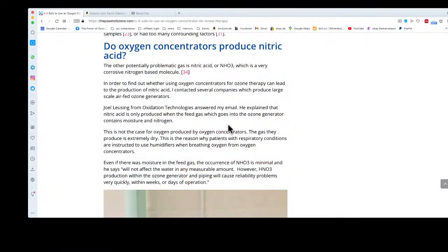So even if nitrogen oxides are produced during the usage of oxygen concentrators, there is no reason to believe that this could be somehow detrimental to your health. And if there is nitric oxide, so NO, this could actually even be beneficial, as crazy as this may sound. But apart from nitric oxide, so apart from NO and NO2, nitrogen dioxide, there's also another gas that can be produced. This is nitric acid, or HNO3. And this is a strong acid, and it is a very corrosive material, and this could be dangerous.